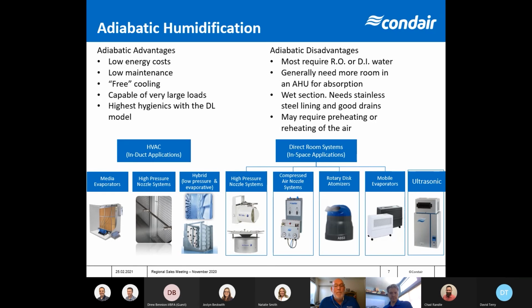This is our DL model. And this one here, we use a low pressure pump, so it's more energy efficient than high pressure. We use a low pressure pump supplied to our nozzles, spray the water into the air and onto our ceramic media. This system has very good controllability. It's not quite as good as the HP because of the time it takes to saturate the ceramic media and then again to dry it out. But it does a great job, very low cost of operation.